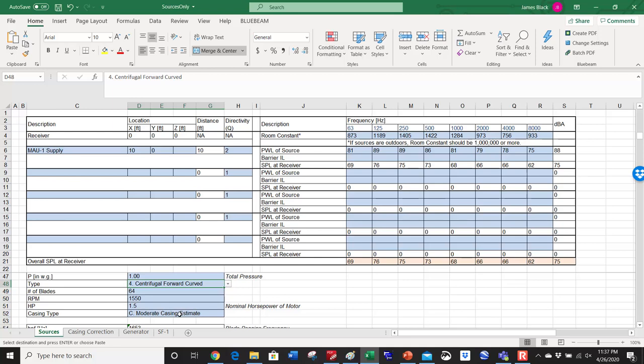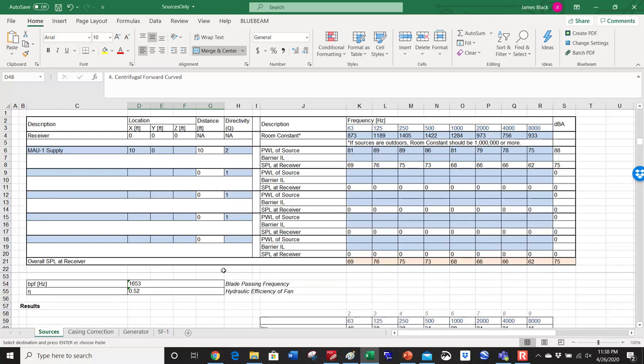is only used for the radiated noise. If you have that bare fan and you want to make a prediction of the radiated noise, then you subtract the casing correction from the bare fan sound power level. Now, I do have quite a few different estimates: a light, a medium, a heavy, and an average of data from different calculations, and all those can be selected with a drop-down menu there.